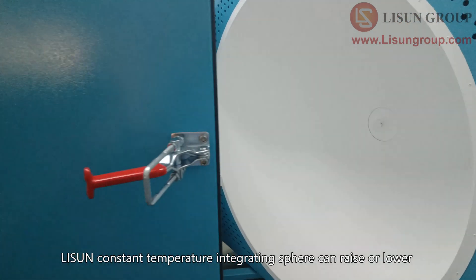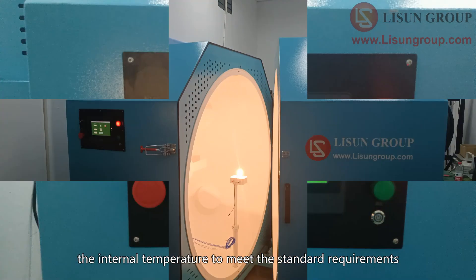According to IES LM82 standard, we also need to do tests at other ambient temperatures to further verify performance. The LISUN constant temperature integrating sphere can raise or lower the internal temperature to meet the standard requirements.